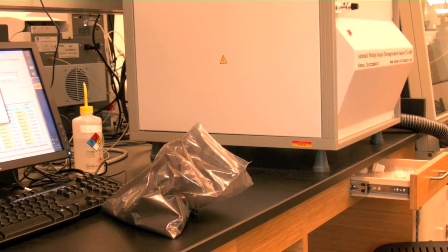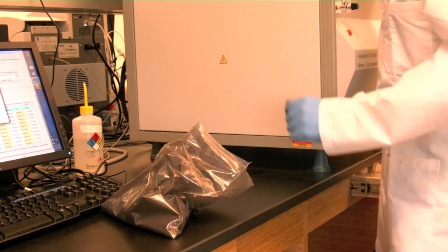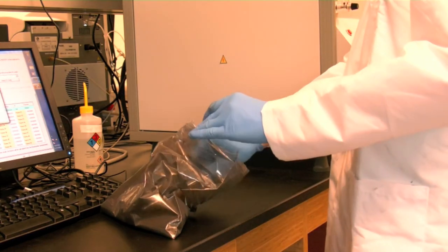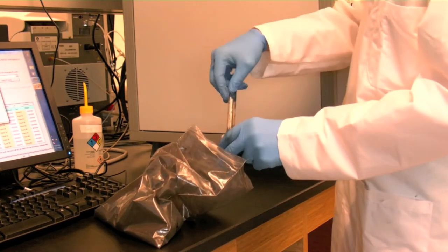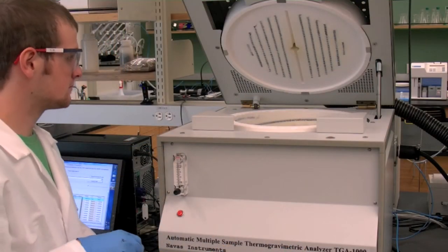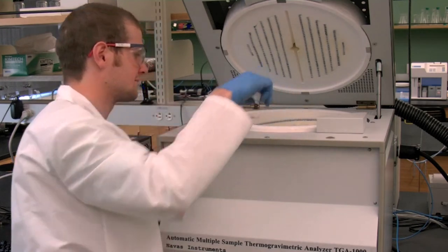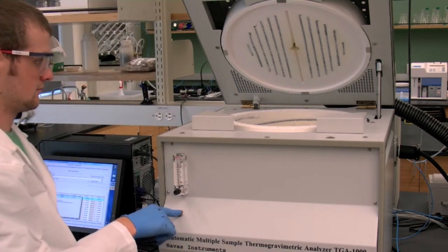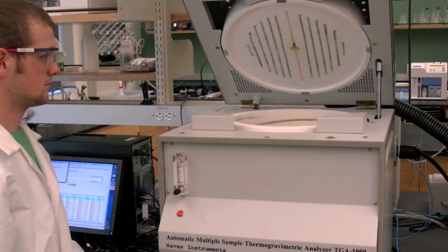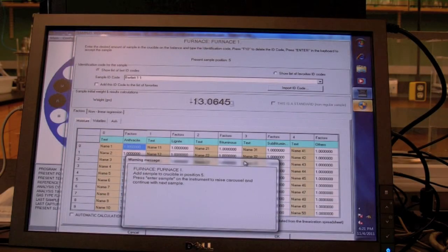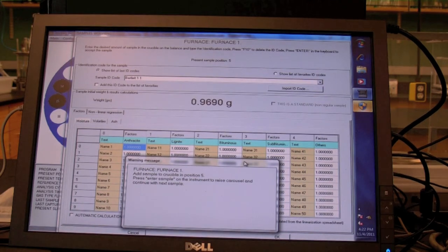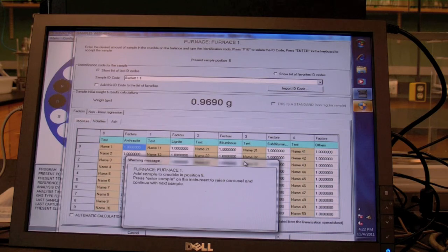Remove the sample crucible from the carousel in the home position and fill it with the desired amount of sample. Put the sample crucible back on the carousel and press the red test weight button. This will lower the carousel setting the crucible on the balance pedestal. The current weight of sample will be displayed in the screen. To change the mass of the sample, remove the crucible from the carousel and add or remove sample.